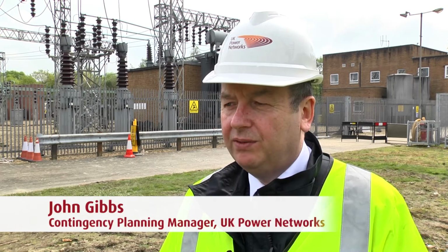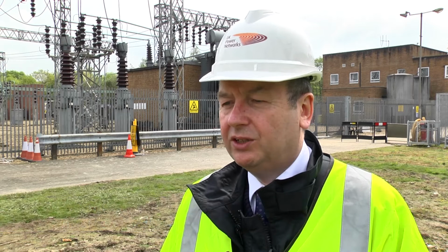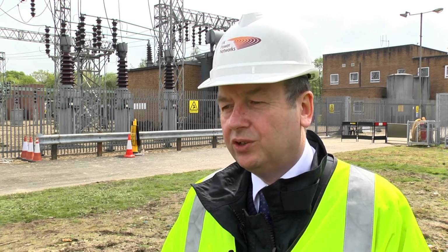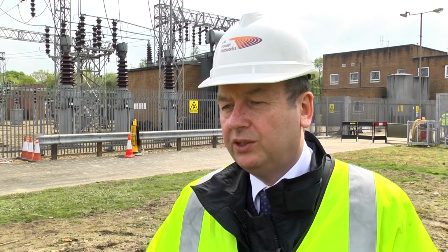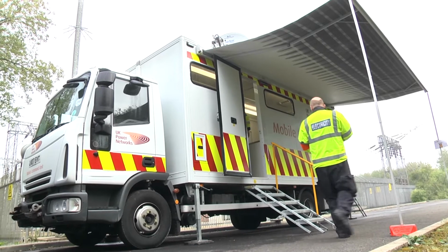We subscribe to the Environment Agency Flood Warning Direct System, which actually sends us an email to say there is a substation at risk. We can look down that list and identify our substations. We can then talk to the Flood Information Duty Officer in the Environment Agency, who will tell us which ones are most concerned to him.